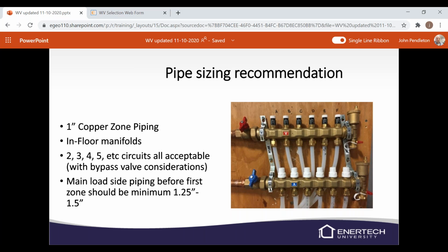You can order these in-floors. You can make your own. It doesn't really matter to me too much. These in-floors are pretty nice. You can order them in however many circuits you need. And I would recommend, if you're running into a bigger manifold, you may want to run 1.25 inches or 1.5 inches copper piping over to it. Check out our IOM. There are some flow rates and pipe sizing recommendations in there. So definitely look in the IOM for proper pipe sizing.